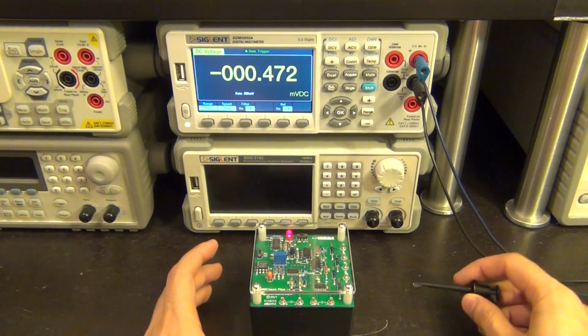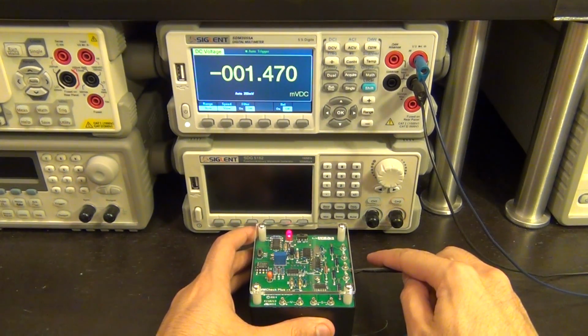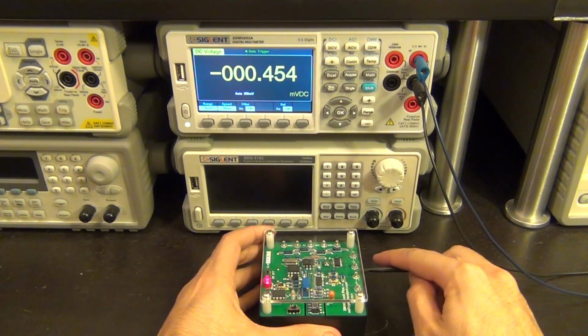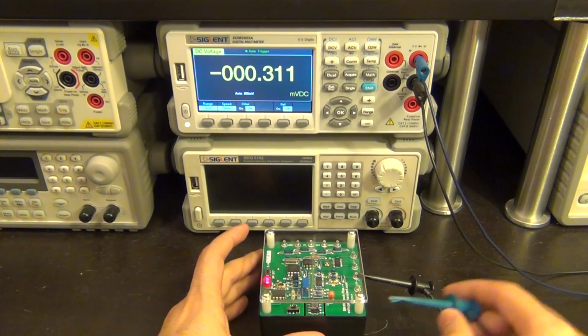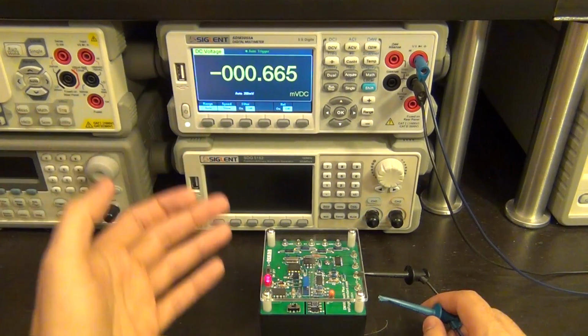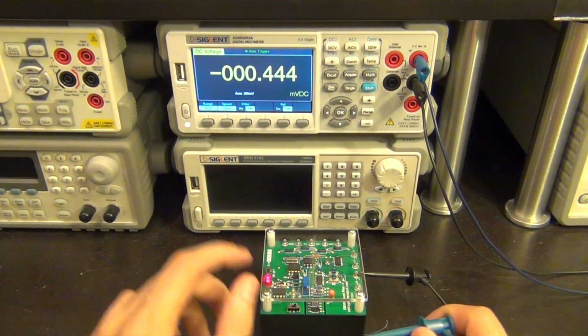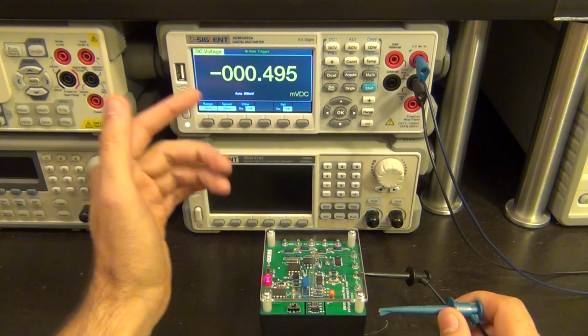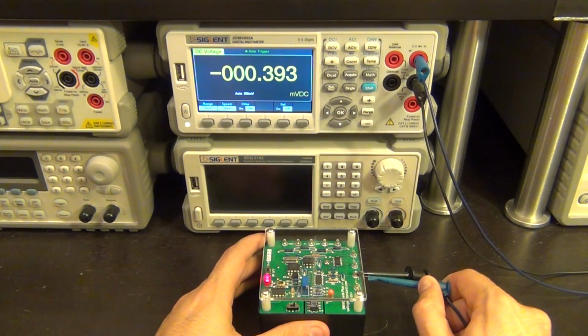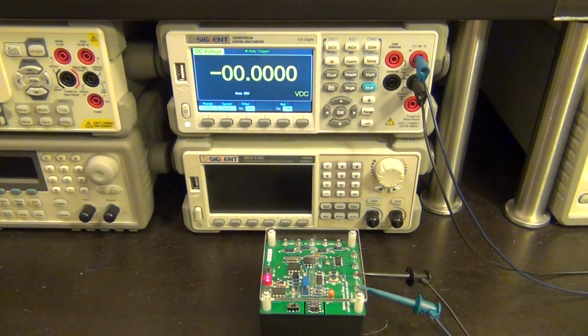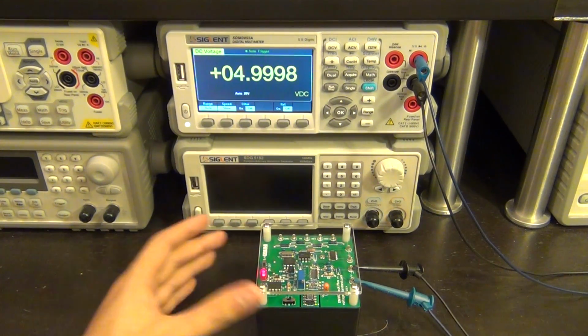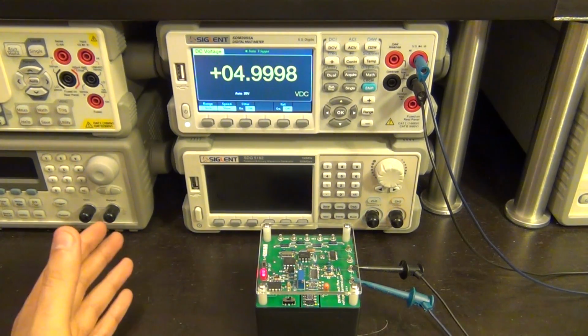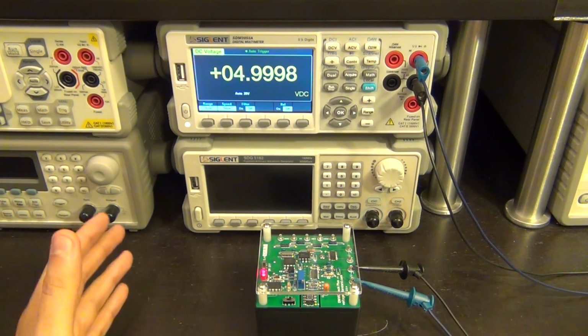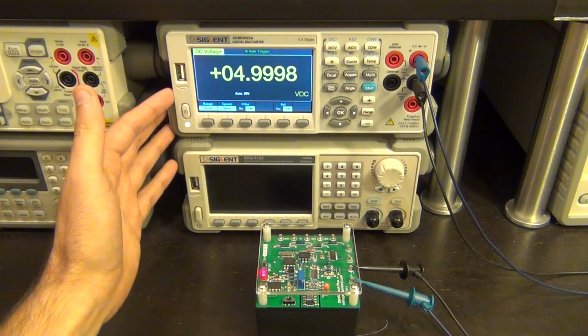So let's go ahead and plug this in and measure it. I'm going to try and measure 5 volts. Let me find the output here. There it is. Now, once I plug in the plus sign, you can correlate that with how long it takes for the instrument to go from the 200 millivolt range to the 20 volt range that it needs to jump to. Here we go. You can see it does take a bit of time, and this is what I was pointing at. If you're okay with that, then it's not a problem. Again, it depends on what you're used to, but other than that, no complaint about any other aspects.